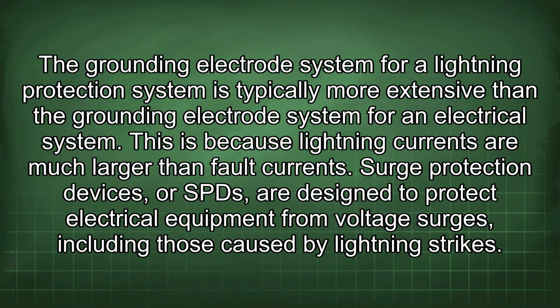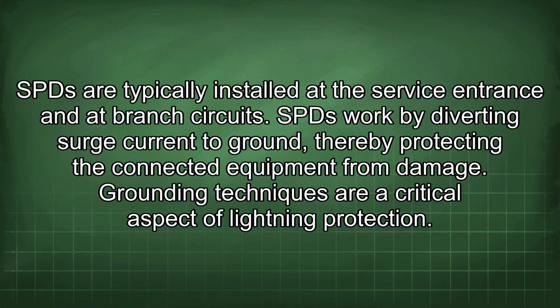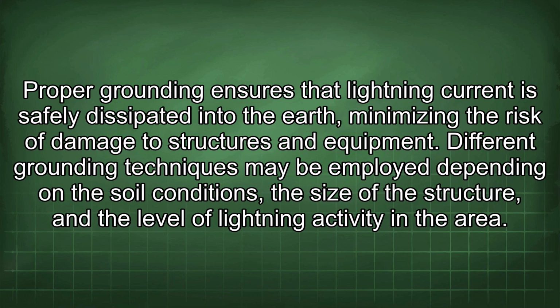Surge protection devices, or SPDs, are designed to protect electrical equipment from voltage surges, including those caused by lightning strikes. SPDs are typically installed at the service entrance and at branch circuits. SPDs work by diverting surge current to ground, thereby protecting the connected equipment from damage. Grounding techniques are a critical aspect of lightning protection. Proper grounding ensures that lightning current is safely dissipated into the earth, minimizing the risk of damage to structures and equipment. Different grounding techniques may be employed depending on the soil conditions, the size of the structure, and the level of lightning activity in the area.